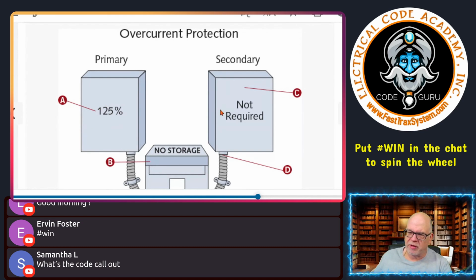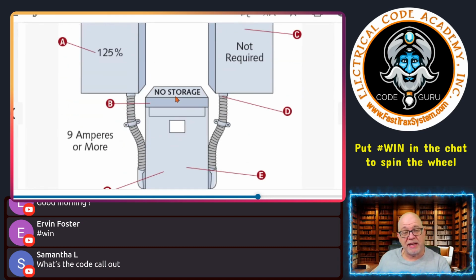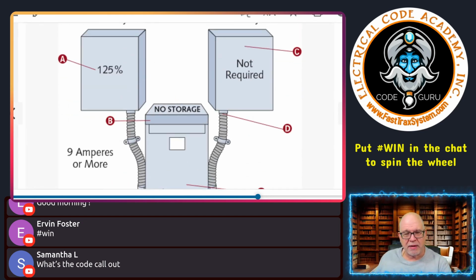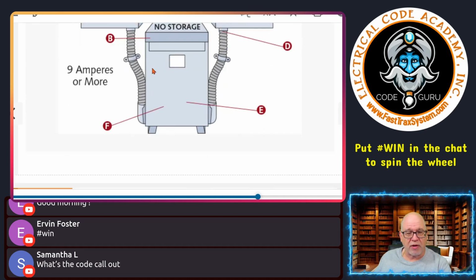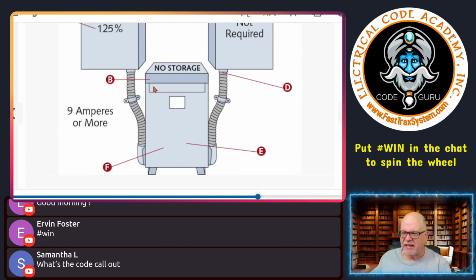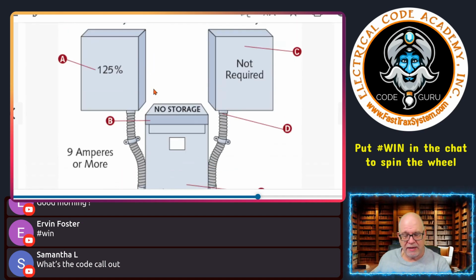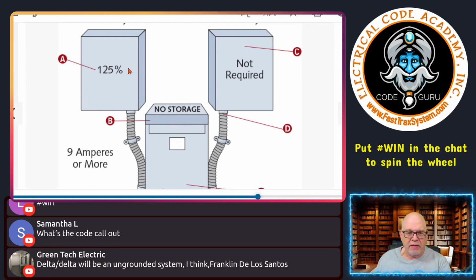So in order to determine this for the transformer, as you know, we need the kVA. We have the kVA divided by whatever the primary voltage is, and that's going to determine our amps. So that is our amps for that transformer. Then we can take that at 125%. Now, what we're saying here is this is primary only protection first. And again, we're talking about protecting the transformer. That's it. Then in this case, I would go to 125%.